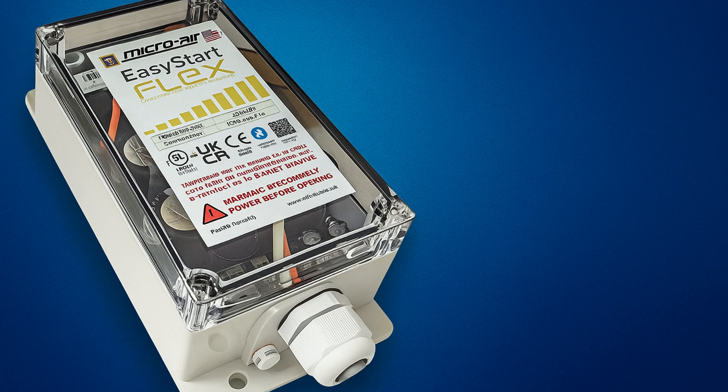Saving thousands is a powerful incentive. New AC units are a major investment — you're talking anywhere from $4,000 to over $10,000, depending on the system and your location. We often see soft start kits extending compressor life by maybe 20% to 30%. So for a unit designed to last 10 to 15 years, that can mean an extra two to four years of life. That's a significant return on what's a relatively small initial investment in the kit — proactive protection for a very expensive appliance.